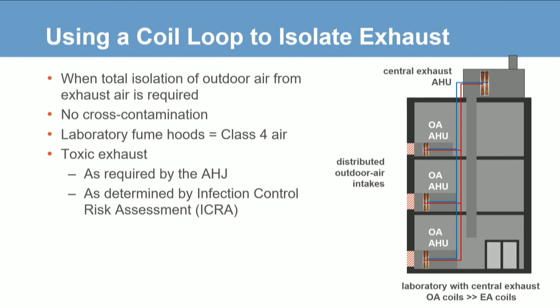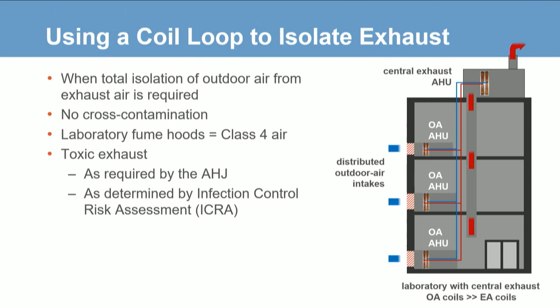The primary advantage of a coil loop is that the exhaust outlets and outdoor air intakes do not need to be near each other. For most laboratories, there will be outdoor intakes spread across the building and various sized outdoor air handlers alongside one central exhaust air handler. The heat exchanger transferring energy from the exhaust air to the outdoor air does not come in contact with the exhaust air — applicable where isolation is required by industry ventilation standards or wherever there is toxic exhaust as determined by the local authority having jurisdiction.